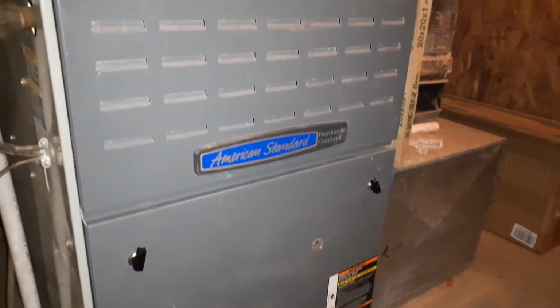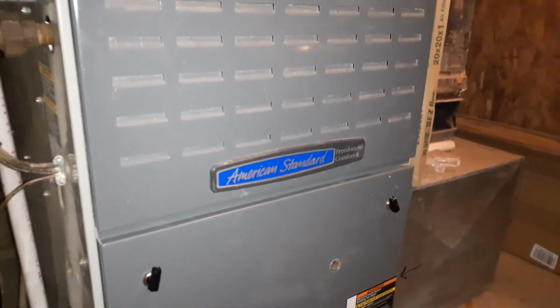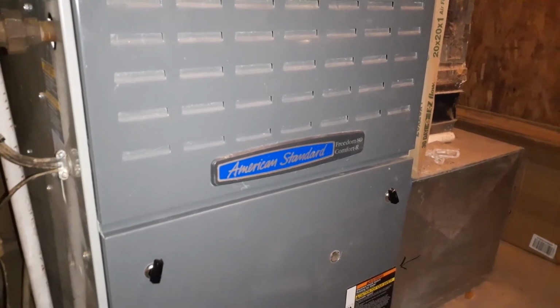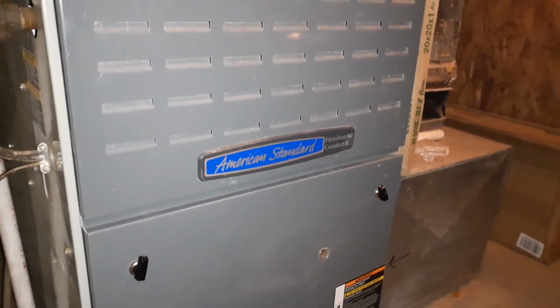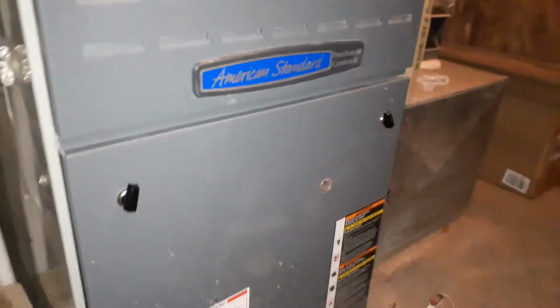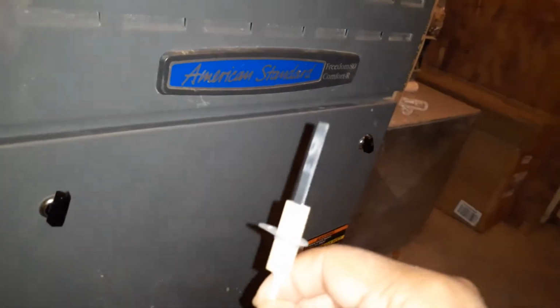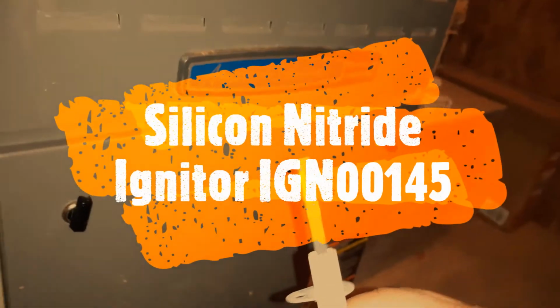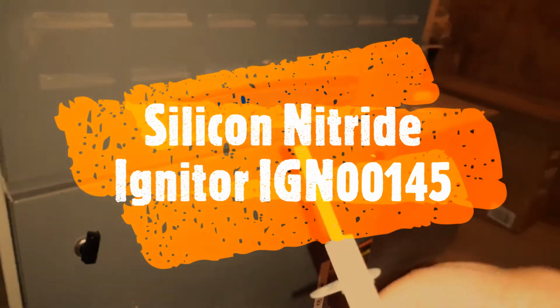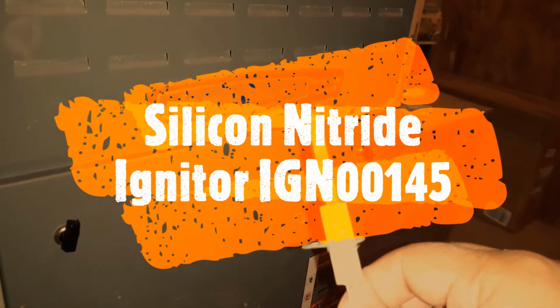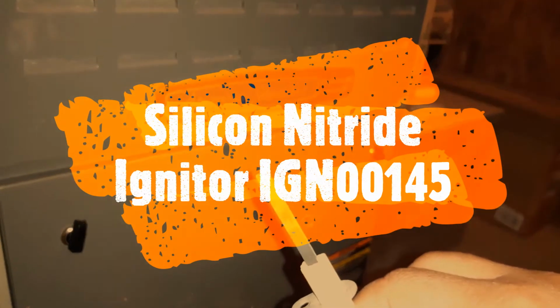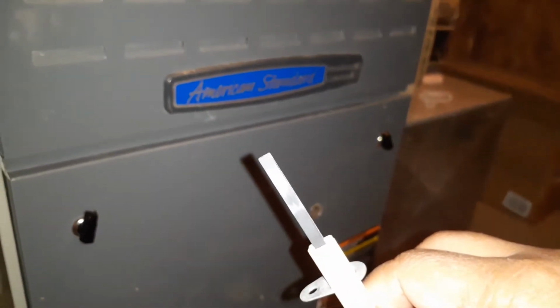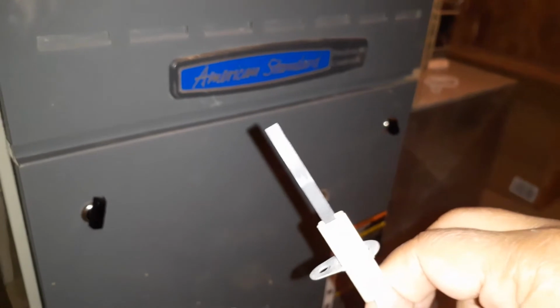Now the igniter is a maintenance part, and it's not going to be beneficial for you to get a used part, because you want to put a new part in there. It's not that expensive, and an igniter looks like this. It has the hot surface igniter. These are the silicon nitride ones, which are the better ones, and these machines being expensive, they use the silicon nitride. The cheaper ones have another type of hot surface, which uses a different material that doesn't last long, but these will last you long.